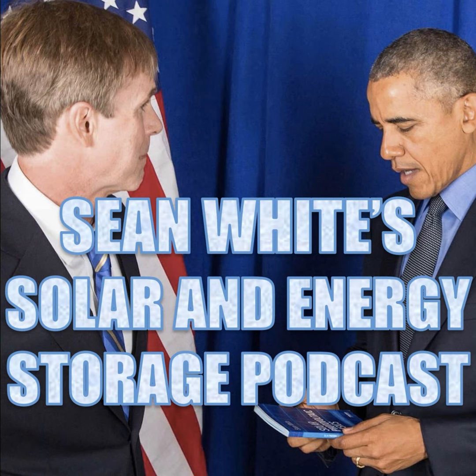These are working spaces. This is so you have room to work on something. And just like with all things that you're doing with equipment in the National Electrical Code, you do 110.26. In fact, I think they almost don't even have to say this because it's just a given. Most people are going to be using the 110.26, which is for conditions under 1,000 volts. But if you were going higher voltage, then perhaps you would go 110.34, which is going to be for things that are over 1,000 volts.